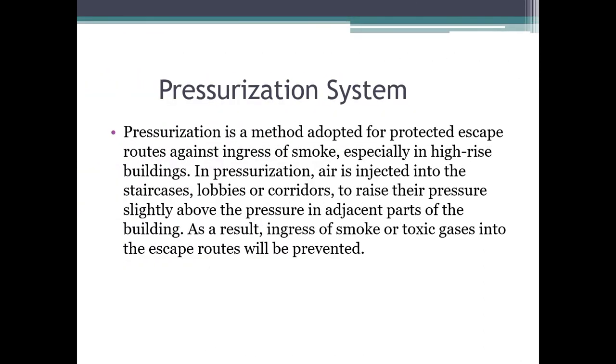Pressurization is adopted for protected escape routes against the ingress of smoke, especially in high-rise buildings. Air is injected into the staircase lobbies or corridors to raise the pressure slightly above the pressure in the adjacent parts of the building, which prevents smoke or toxic gases from entering the escape routes and prevents people from suffocating inside the corridors or staircase areas.